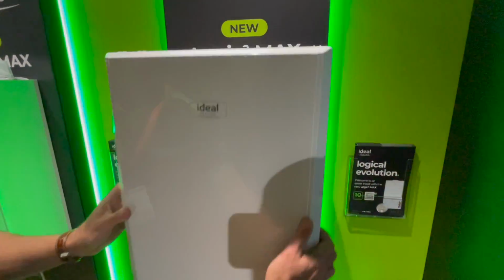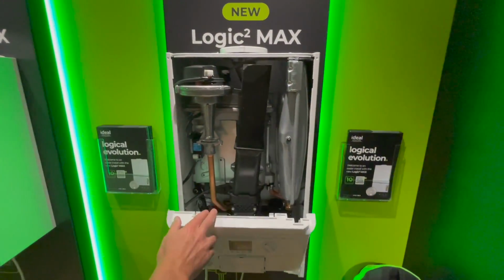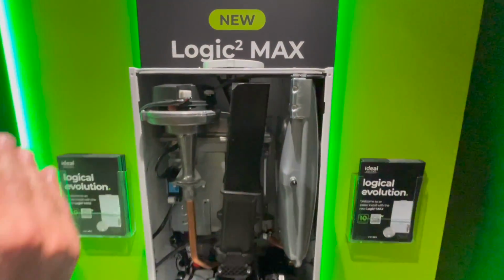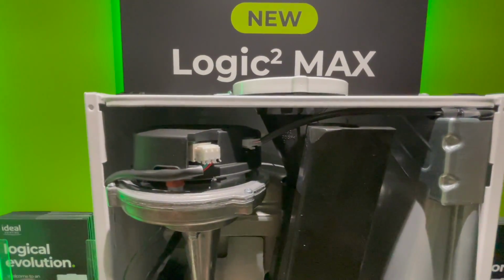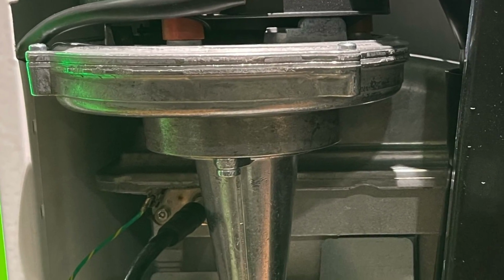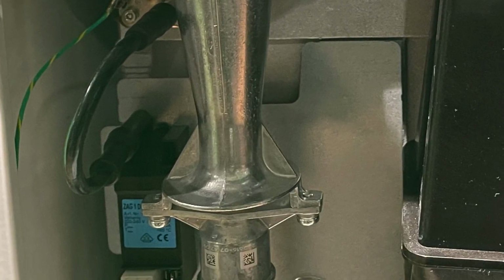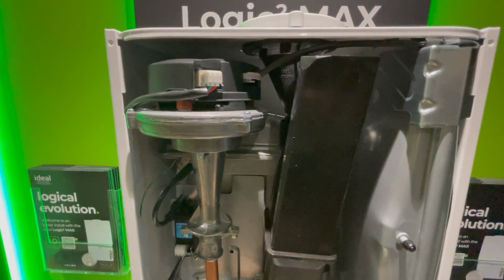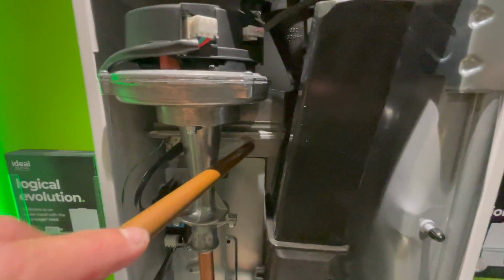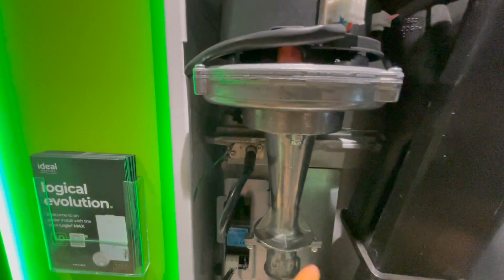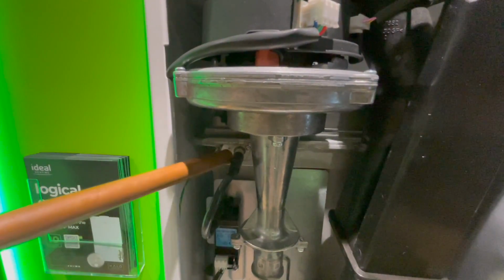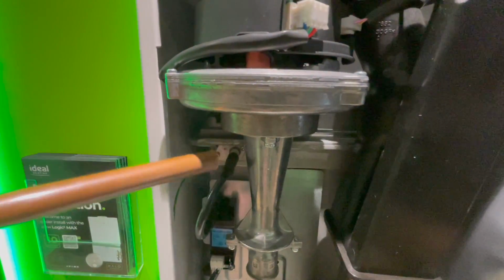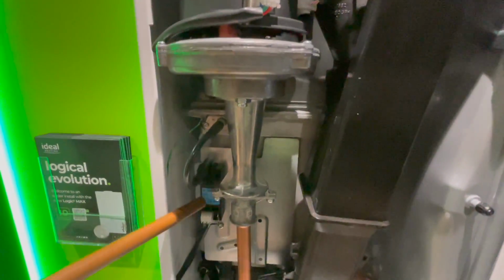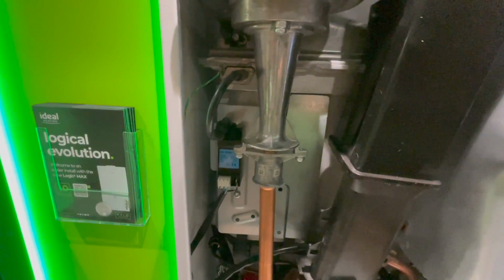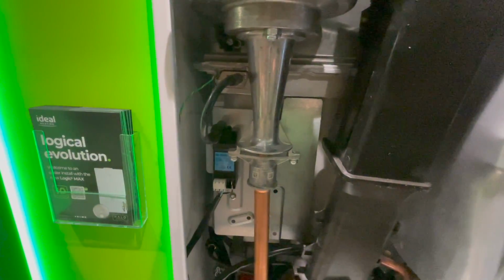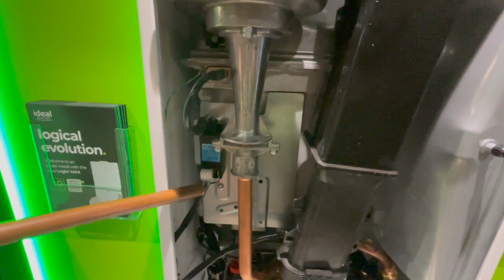So if we remove the cover, we can have a look at the changes inside the boiler. The first thing is there's a new fan. It's made by the same company as the old fan, but it's just a little bit quieter. Just down from the fan you can see there's an electrode missing. So they've gone to 1 electrode now instead of 2. This electrode is like a lot of boilers where it'll do the ignition and flame rectification. There's also a new spark generator, which is the one they use on the Vogue boiler.